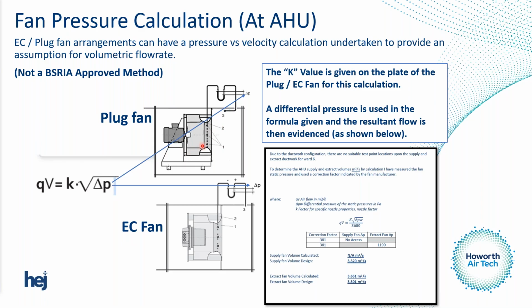Within the fan, you can see here that's the motor, and the impeller sits on this side. This has a driver that's connected, and I'll talk to you more about EC fans later in the slides, but there's a driver connected there to the impeller, and then there's a pressure loop that sits on this side of the fan. We can connect a micromanometer across that to get a delta P, or a difference in pressure. We take that difference in pressure, multiply that by the K factor that is given on the side of the fan, and that will give you a flow rate in meters cubed per hour.